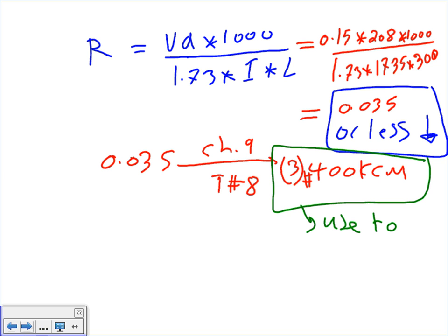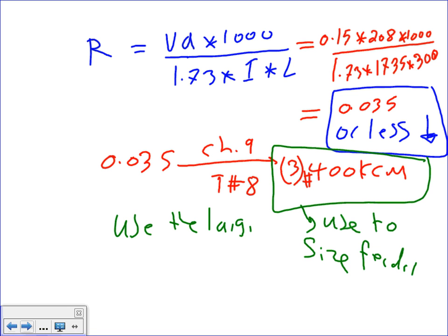Use it to size the feeder, right? Because it's the largest. I'm going to write myself a note here: use the largest of the 3 calculations.